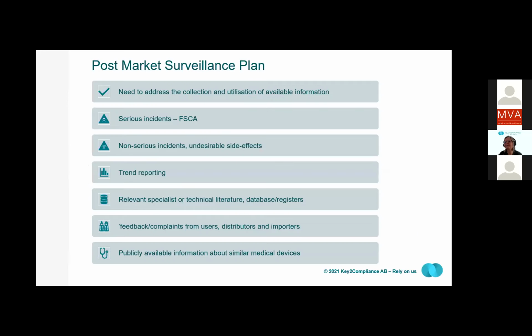The post-market surveillance plan needs to address the collection and utilization of available information, and in particular, the serious incidents, the FSCA, non-serious incidents, undesirable side effects, trend reporting, relevant specialist or technical literature, database registers, feedback and complaints from users, distributors, and importers, and publicly available information about similar medical devices.